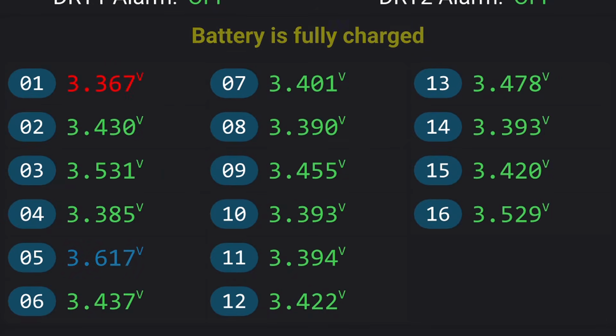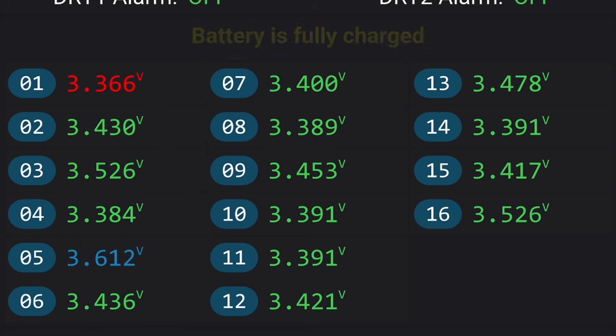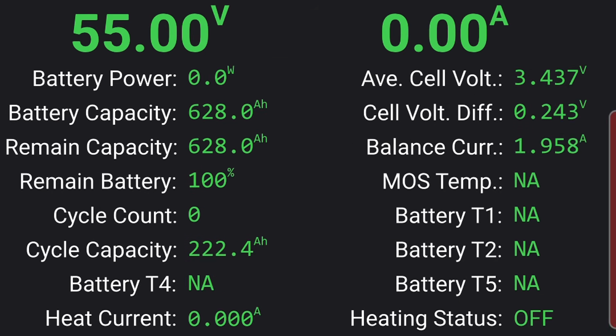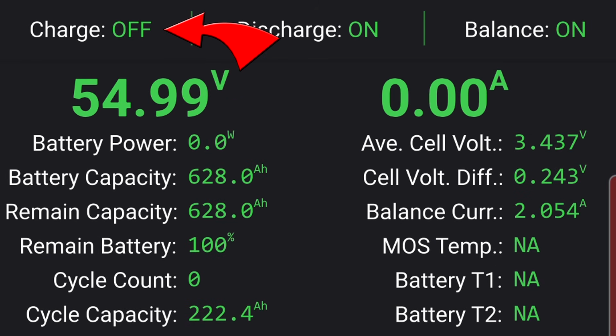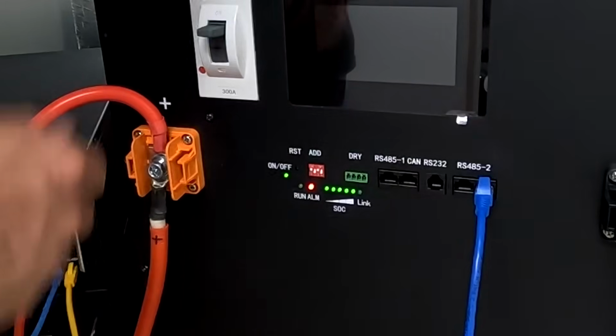Alright, there we have it - we have a cell overvoltage alarm. It says the battery is fully charged, but that doesn't reflect the real cause. We've got overvoltage protection on cell number 5, so the charge MOSFET is obviously turned off, and we can see the red alarm light here.